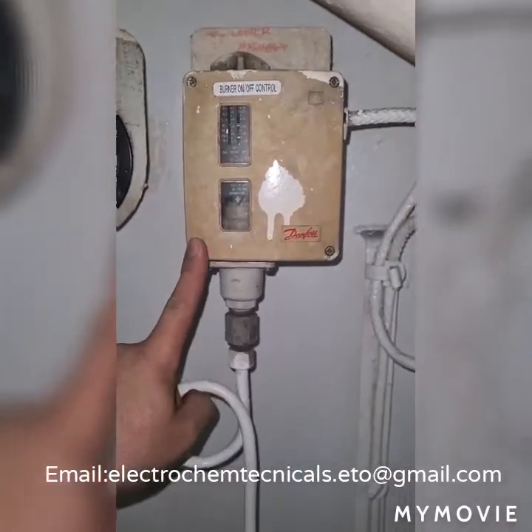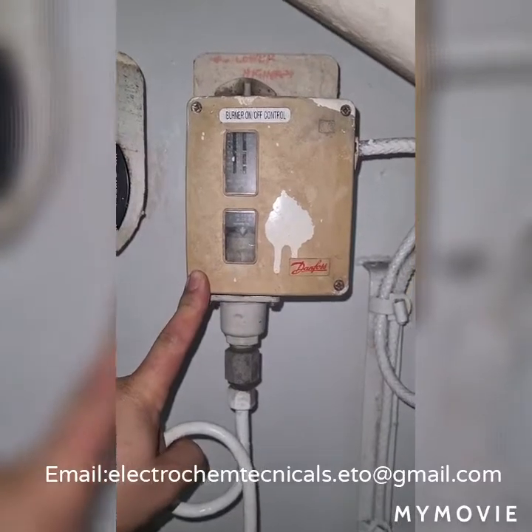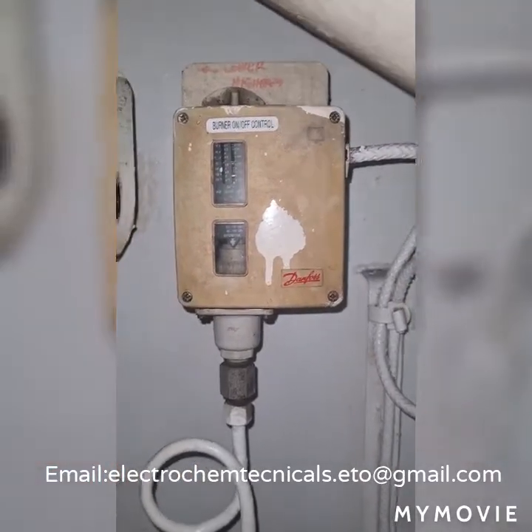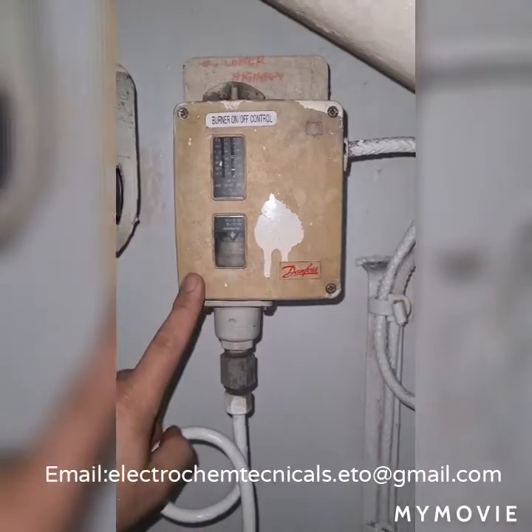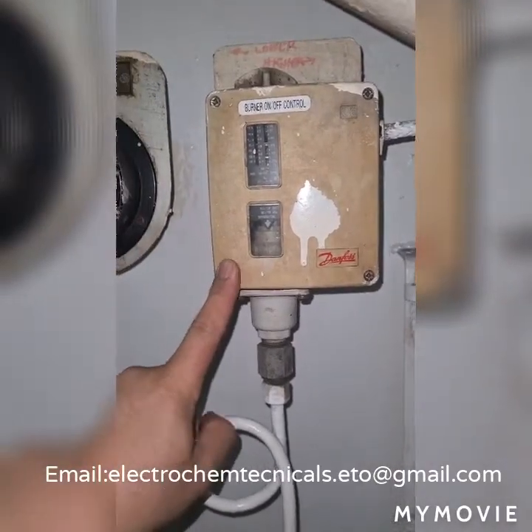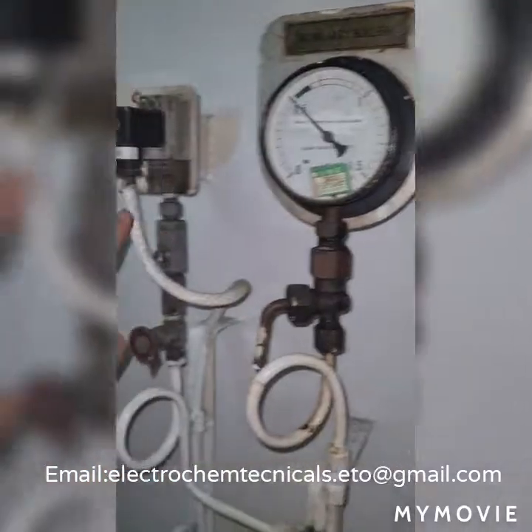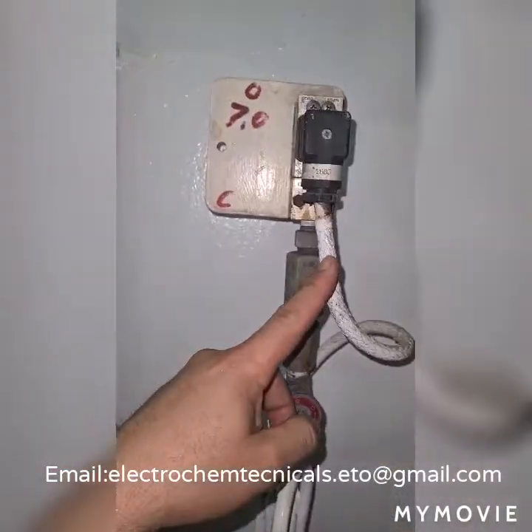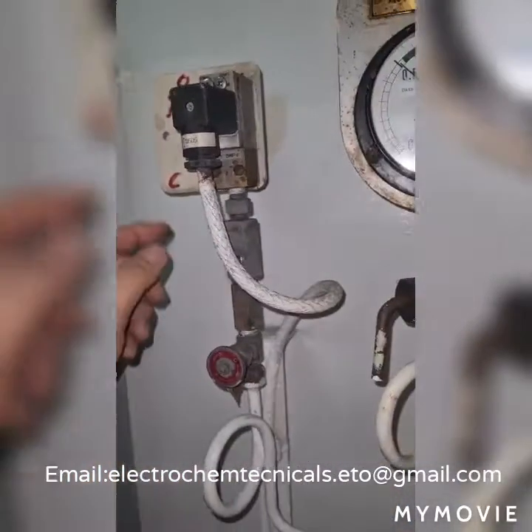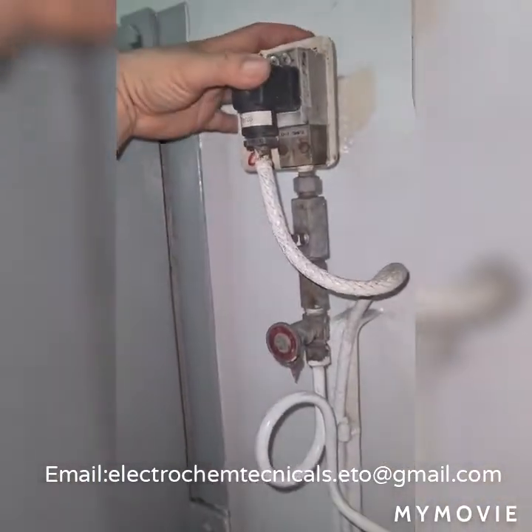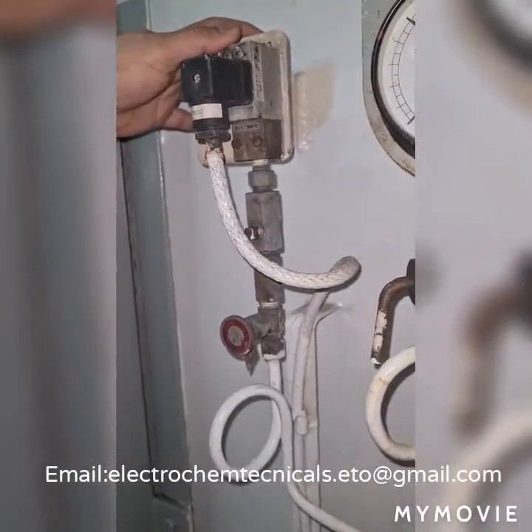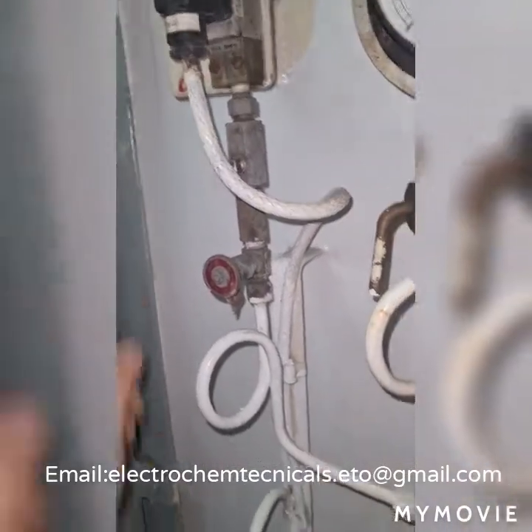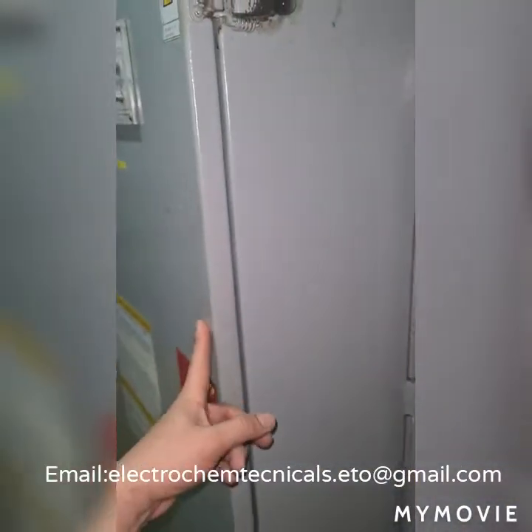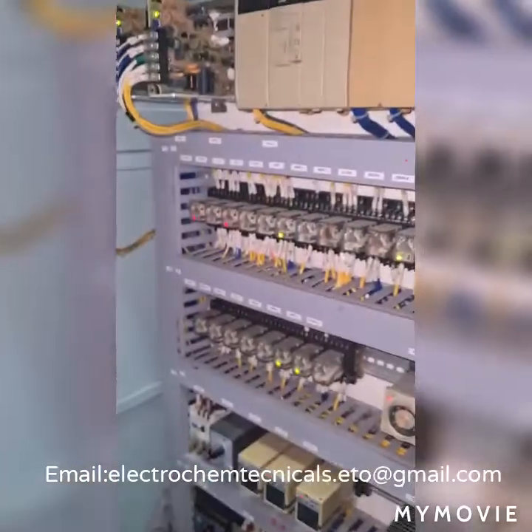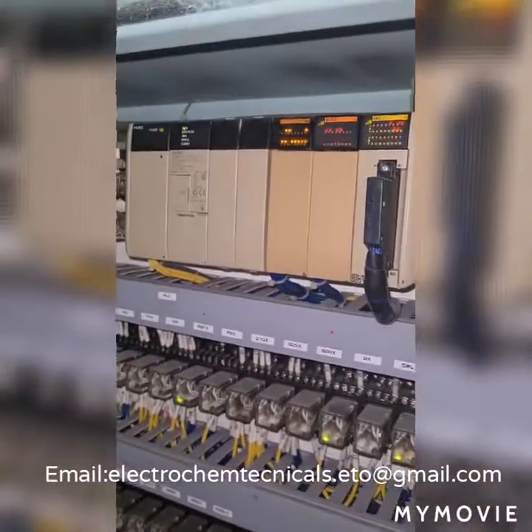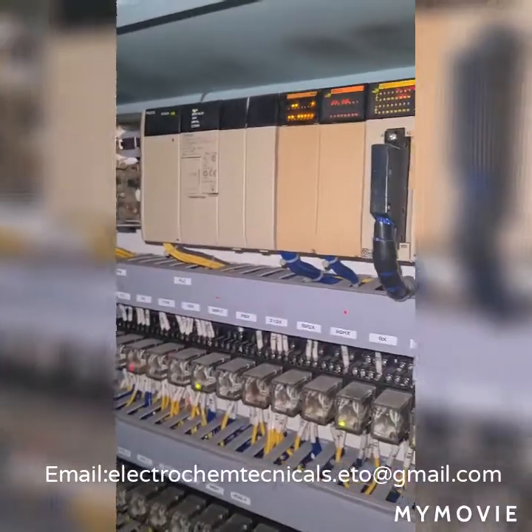This is the pressure switch from which, if the pressure drops from 0.6 to 0.45, it will automatically start the boiler. And this is the pressure transmitter from which the pressure is sent by this transmitter device as a signal to the PLC input of this control panel for the boiler. This is the PLC of the boiler controller.